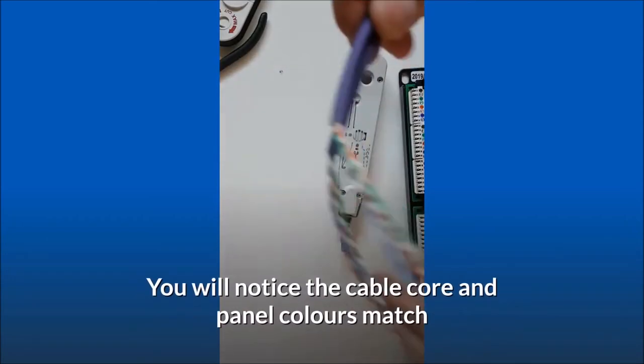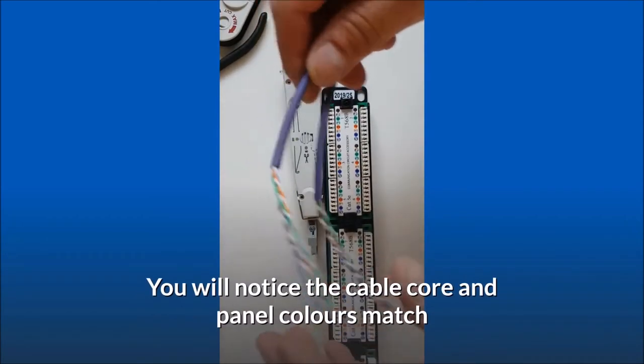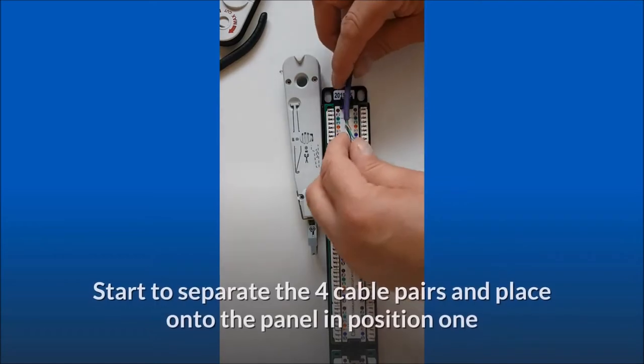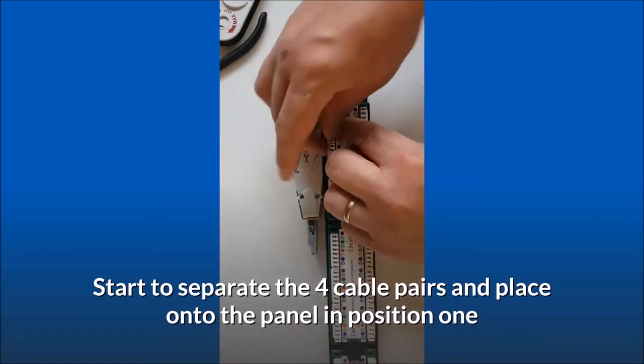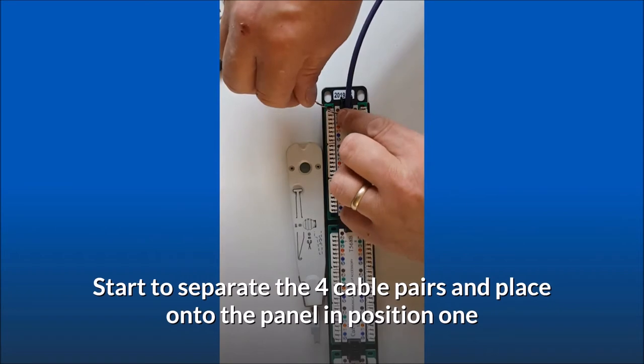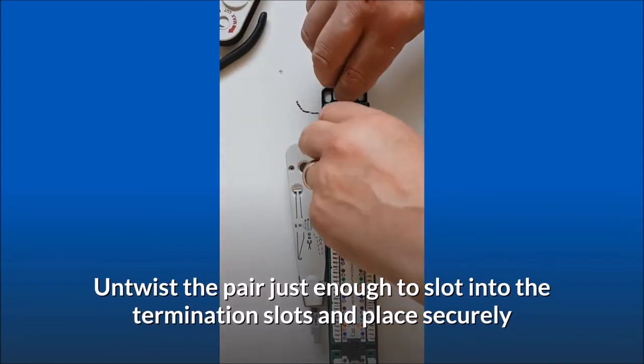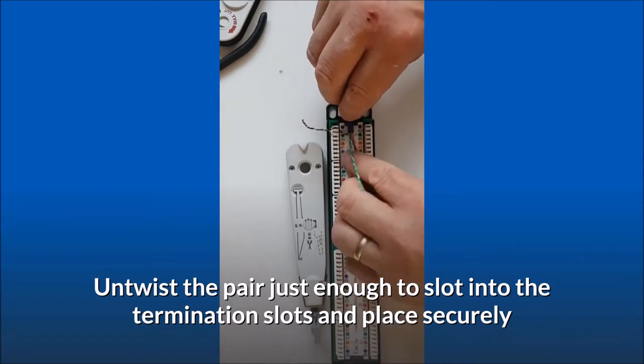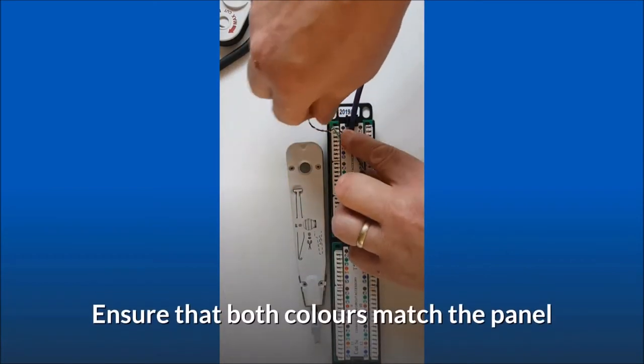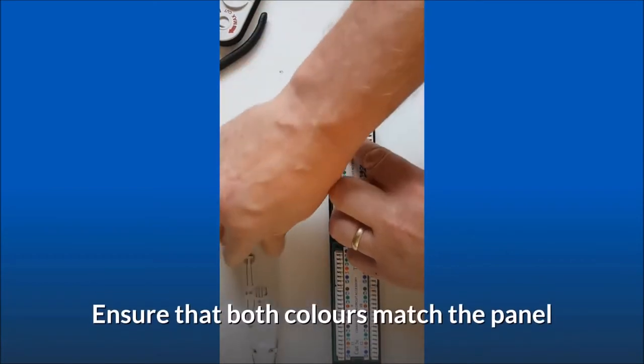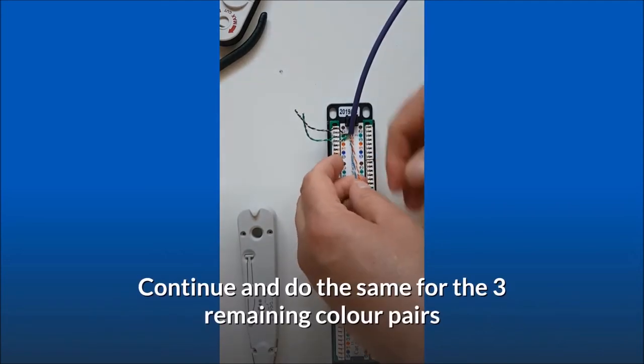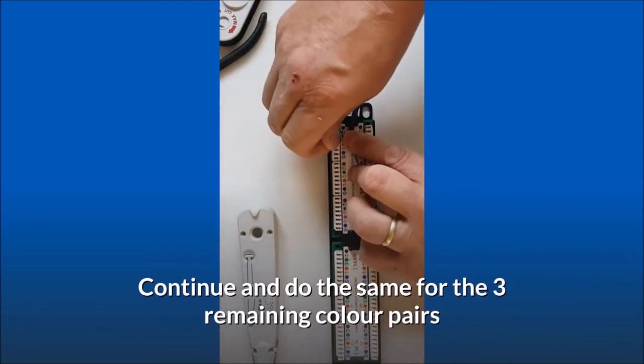You will notice the cable core and panel colors match. Start to separate the four cable pairs and place onto the panel in position 1. Untwist the pair just enough to slot into the termination slots and place securely. Ensure that both colors match the panel. Continue and do the same for the three remaining color pairs.